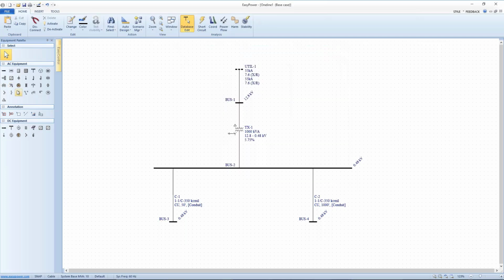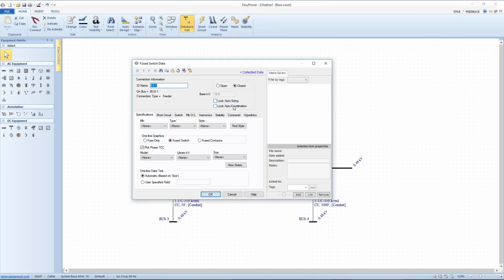Now, the reason I like this example is because it had one protective device in the system, and it was a fuse in his utility cutout switch. So we're going to pick up the fuse icon over here on the equipment palette, put it into the utility bus right here, and then double click on it to open it up.